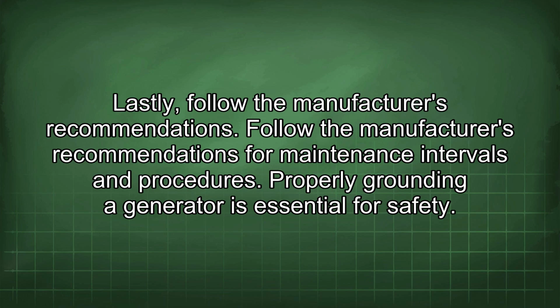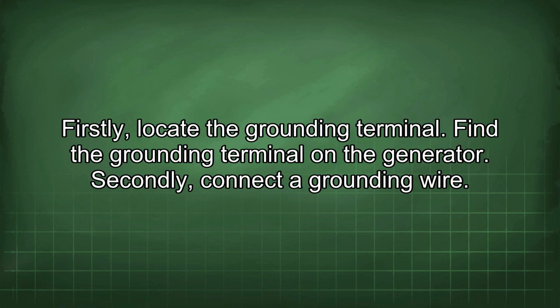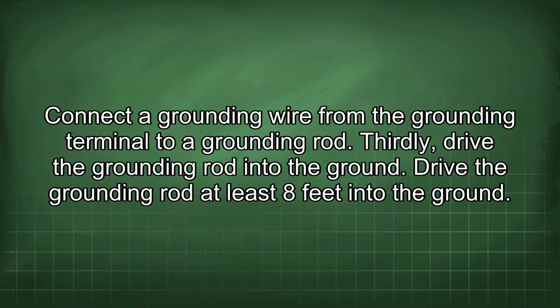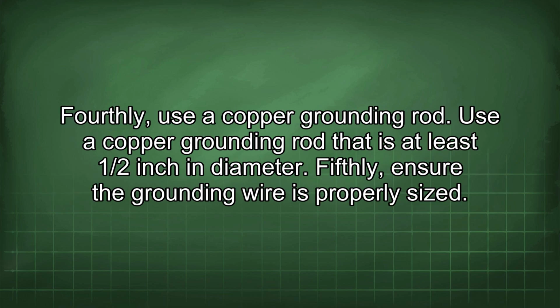Properly grounding a generator is essential for safety. Firstly, locate the grounding terminal. Find the grounding terminal on the generator. Secondly, connect a grounding wire. Connect a grounding wire from the grounding terminal to a grounding rod. Thirdly, drive the grounding rod into the ground. Drive the grounding rod at least 8 feet into the ground. Fourthly, use a copper grounding rod. Use a copper grounding rod that is at least 1/2 inch in diameter.